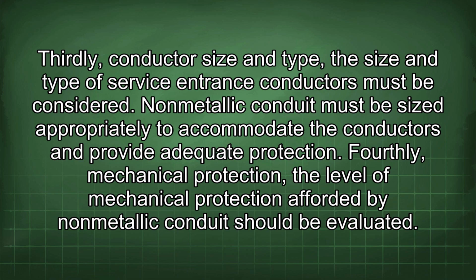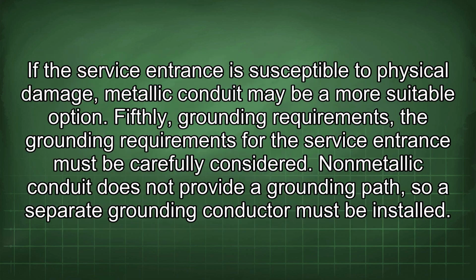Thirdly, conductor size and type. The size and type of service entrance conductors must be considered. Non-metallic conduit must be sized appropriately to accommodate the conductors and provide adequate protection. Fourthly, mechanical protection. The level of mechanical protection afforded by non-metallic conduit should be evaluated. If the service entrance is susceptible to physical damage, metallic conduit may be a more suitable option. Fifthly, grounding requirements. The grounding requirements for the service entrance must be carefully considered. Non-metallic conduit does not provide a grounding path, so a separate grounding conductor must be installed.